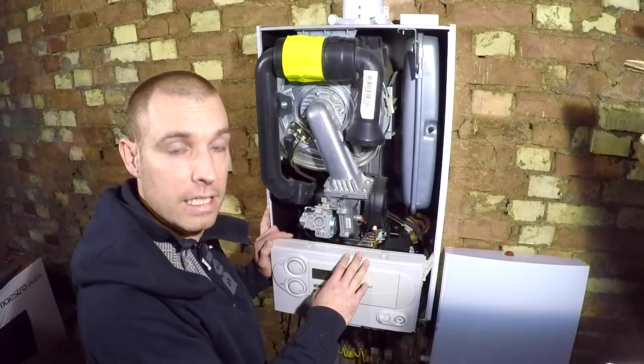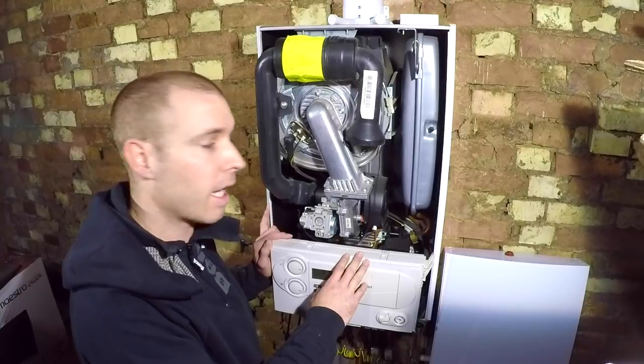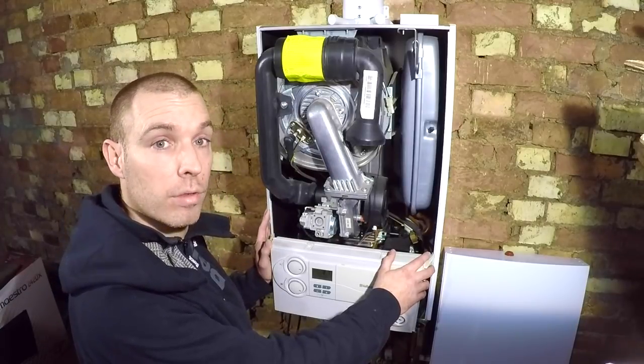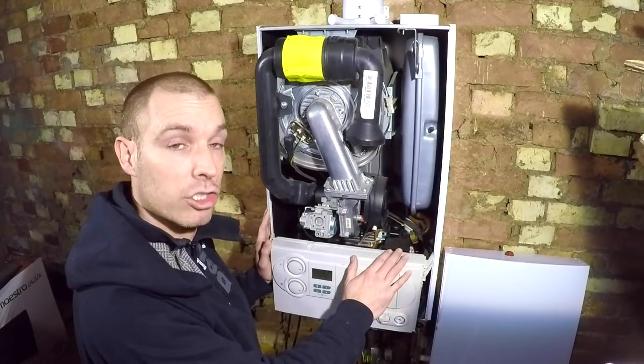I'm going to take a day off work next week to do this and upload the video. I was going to try and do it all today but setting up in this dark loft took a long time, so I've lost a good few hours. But now I know how to set it up it'll be much quicker next time. Next time you see me at this boiler I'll be isolating it, putting a load of descaler in it and running it to see if we can get that issue resolved. Also, this is a boiler with a burnt or blocked coil - you can see it's browner than the rest. Two coils next to each other are brown - a coil is three rings in length - and that's how you can visually identify one. That coil will be overheating and making noise, but the boiler works fine. That's the thing with Vaillants: they will still work with a blocked coil, they just become noisy.